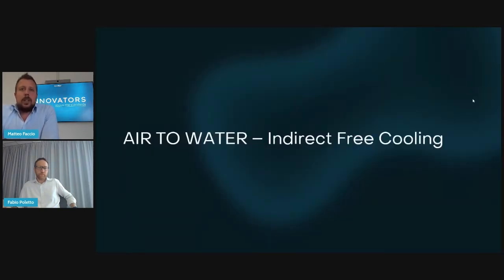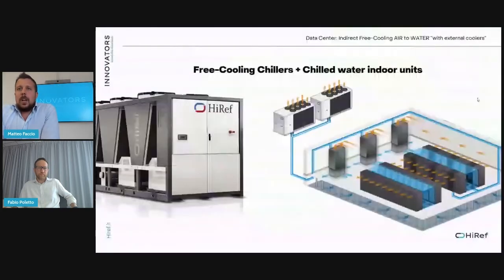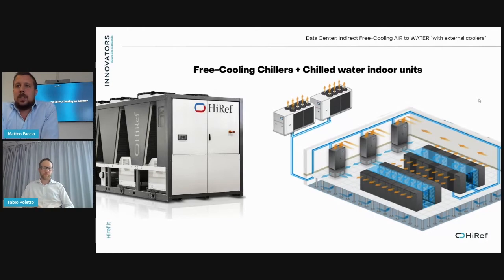Moving to indirect free cooling in the air-to-water version. In this case, we are talking about a more conventional system to produce the cooling. Of course, we will have outside free cooling chillers or other types of units, such as dry coolers or cooling towers. Inside the data center, we will have units able to distribute this capacity. But the most interesting thing in this argument is that, thanks to the higher temperature inside the white space, we can increase the temperature level of the water loop to really high values, such as 30 or 32. This gives the possibility to extend the number of hours that the unit is able to work in free cooling mode.